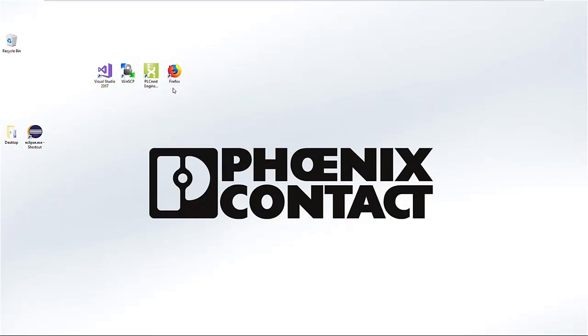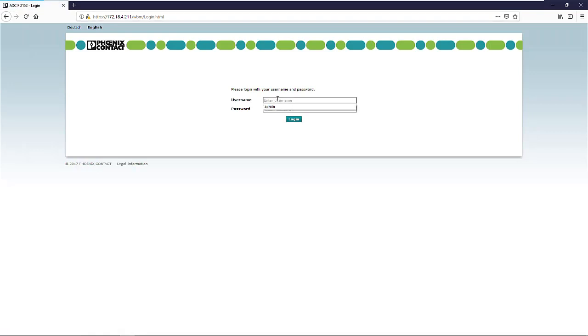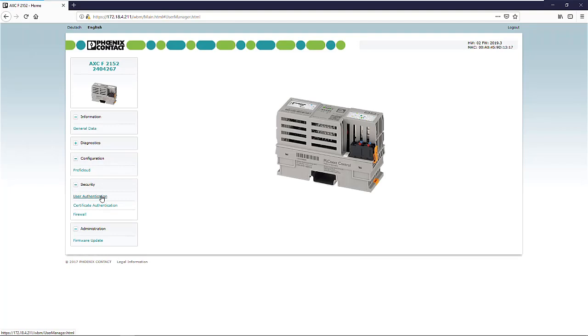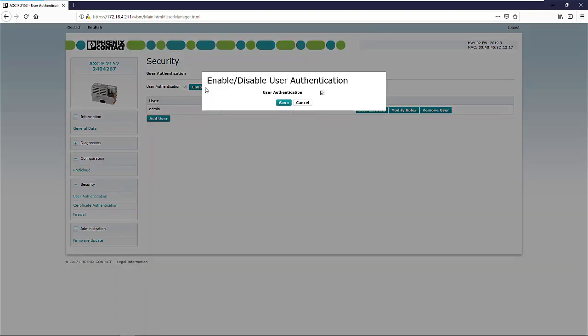Because the remote debugging does not currently support user identification, we have to open the web-based management of the PLC, type in the IP address of the device, enter your user credentials, go to user identification and disable it there, then save and leave the web-based management.